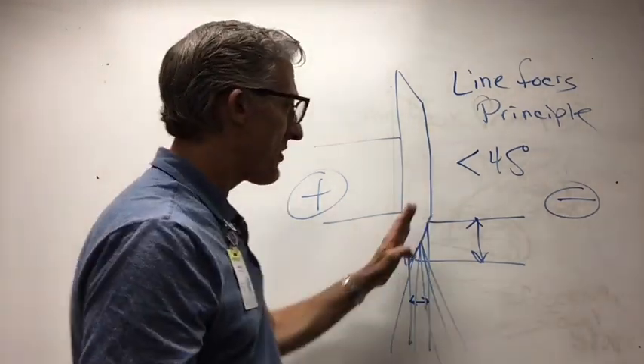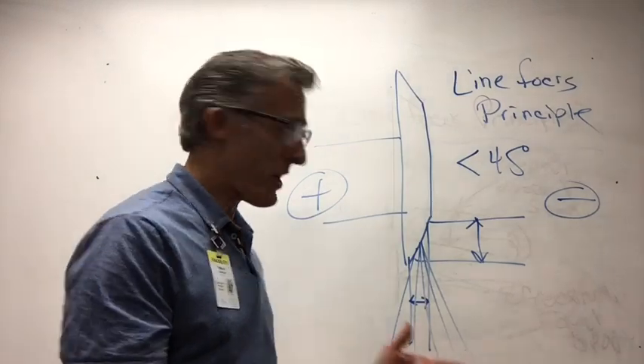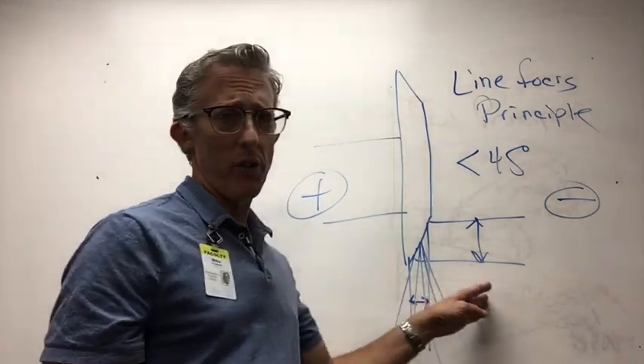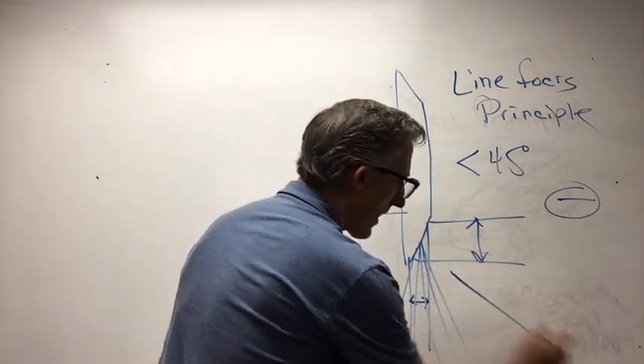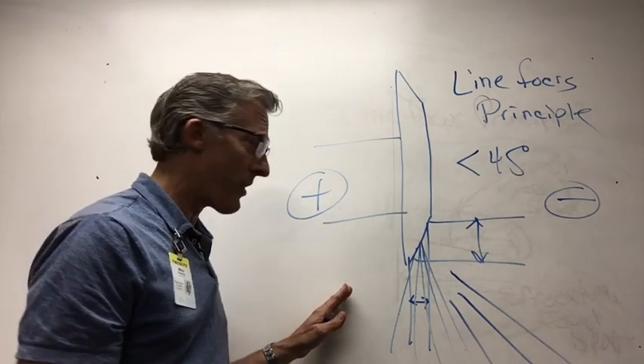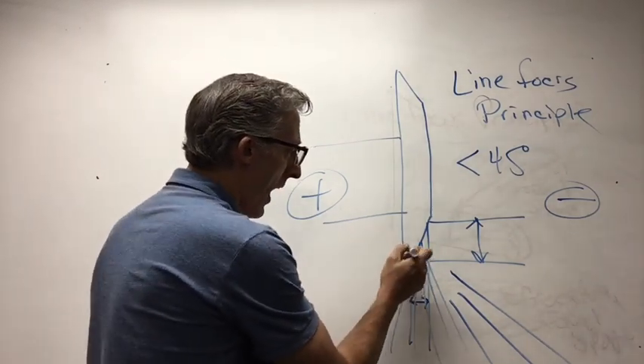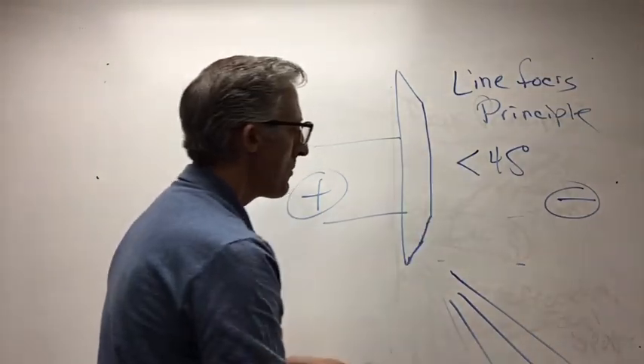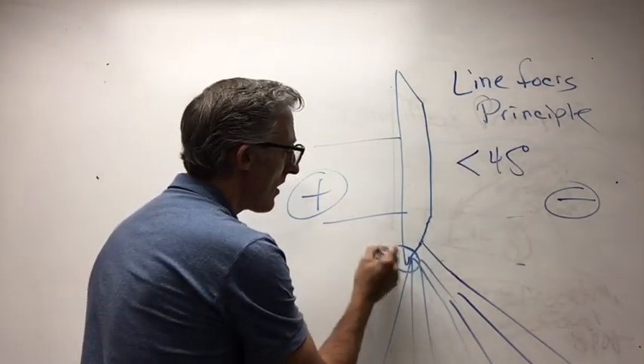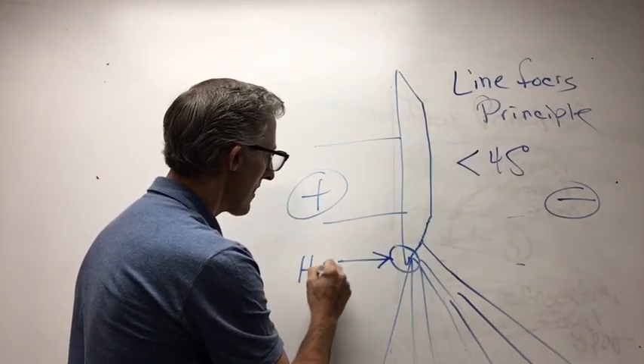Simple, folks. Check it out. This steep angle results in more x-ray photons, a greater number of them, coming off on the cathode side of things. But over here on the anode side of things, some of them are absorbed in what we call the heel of the anode. So if you imagine, you've got x-rays being created, some of them are being absorbed in the heel, heel of the anode.